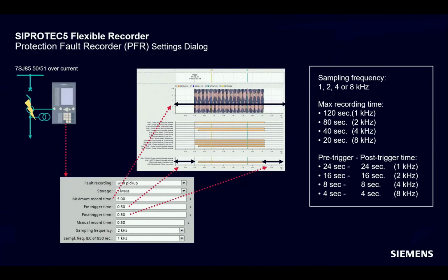Here is a screenshot of the settings dialog of the PFR with a pre- and post-trigger as well as sampling frequency parameter. On the right side of the page, you can see that the maximal recording duration as well as the pre- and post-trigger time depends on the chosen sampling frequency.